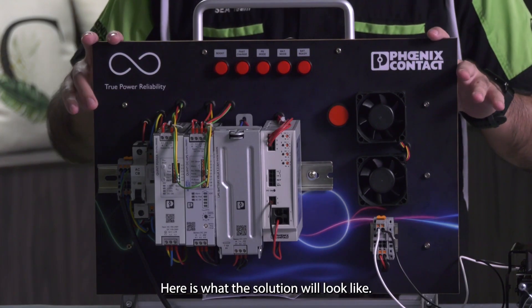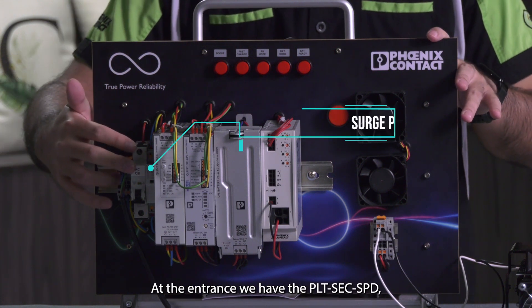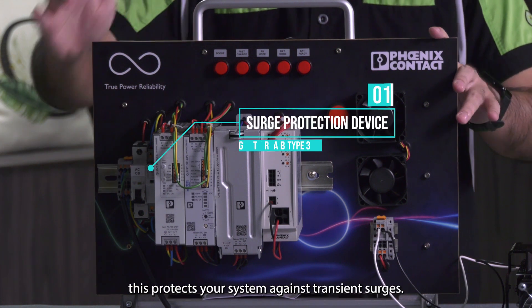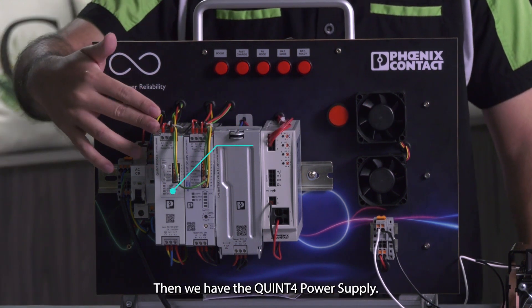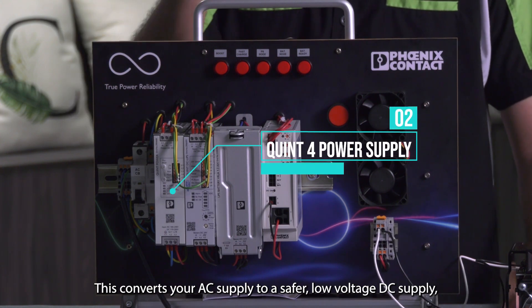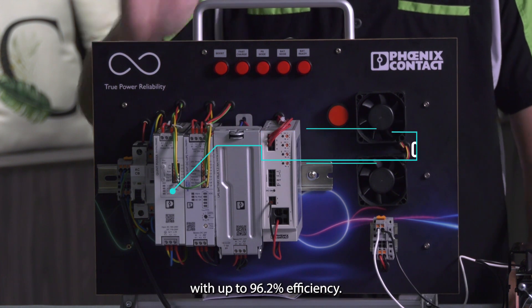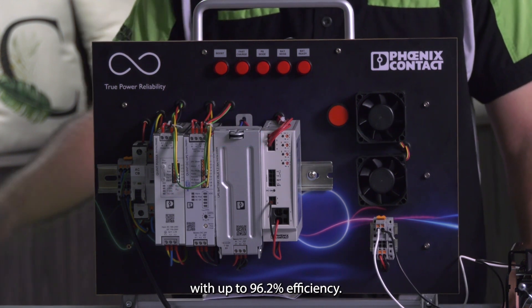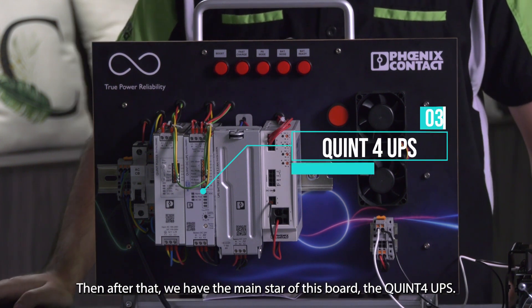Here's what the solution will look like. At the entrance, we have the PLTSEC SPD. This protects your system against transient surges. Then we have the QUINT4 power supply. This converts your AC supply to a safer low voltage DC supply with up to 96.2% efficiency. Then after that, we have the main star of this board, the QUINT4 UPS.